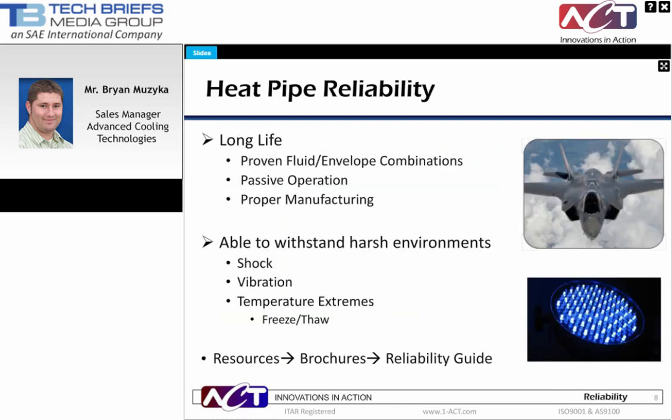One of the more frequent questions on heat pipes is how reliable they can be. Due to heat pipes' passive operation and known compatibility for various fluid and envelope materials, heat pipes provide very long life when manufactured properly. Twenty-plus years of operation is routine for heat pipes. We also need to make sure that the heat pipes can operate in any environment. Heat pipes themselves are thin-walled tubing; however, when integrated properly, they can withstand harsh environments, including requirements such as shock, vibration, and extreme temperatures. Copper water heat pipes are typical for terrestrial applications and have demonstrated the ability to withstand freeze-thaw cycles on their own or when integrated into assemblies such as a high-K plate. We also offer a reliability guide in the resource section of our website.